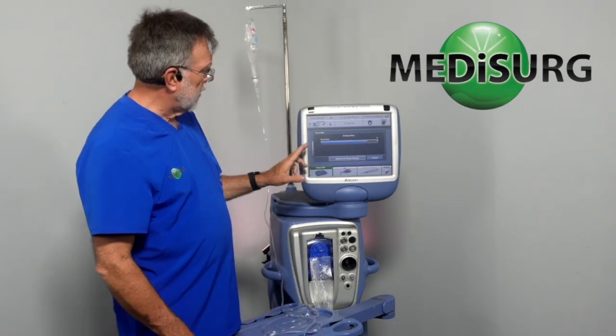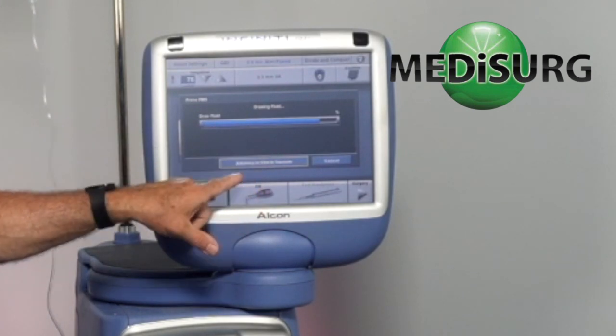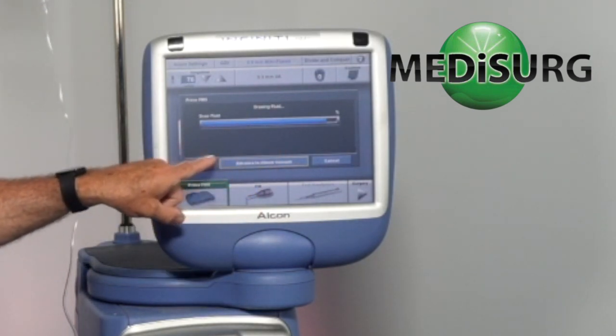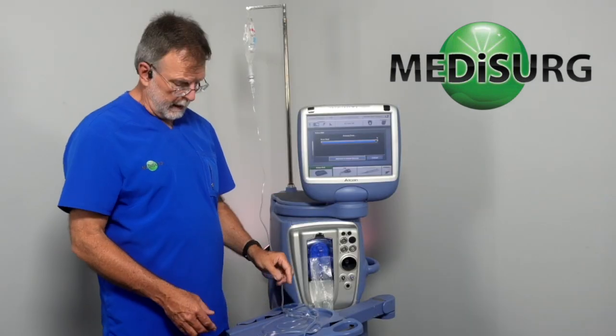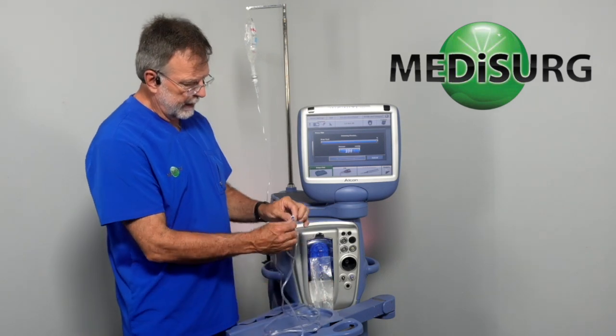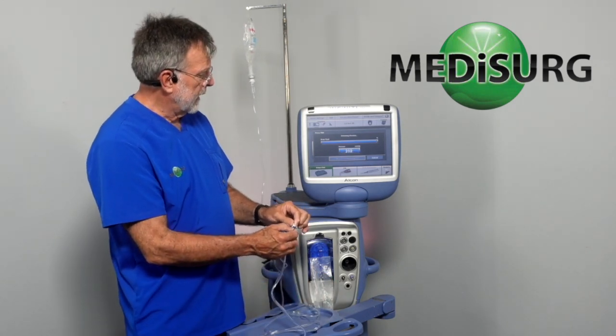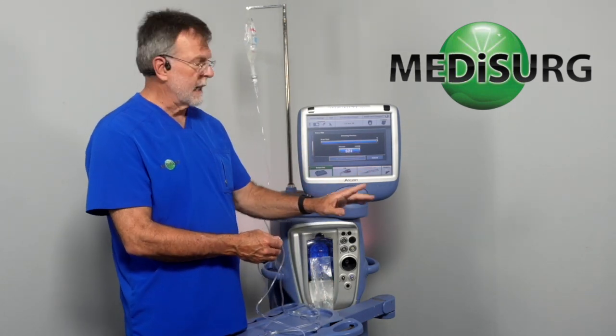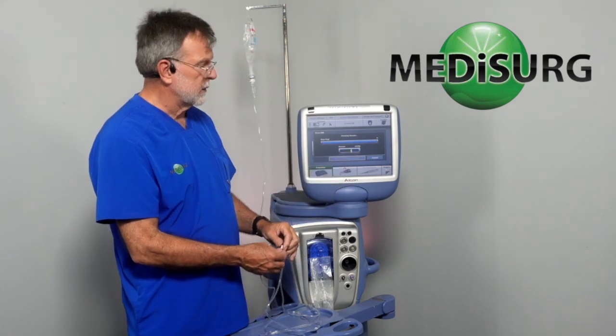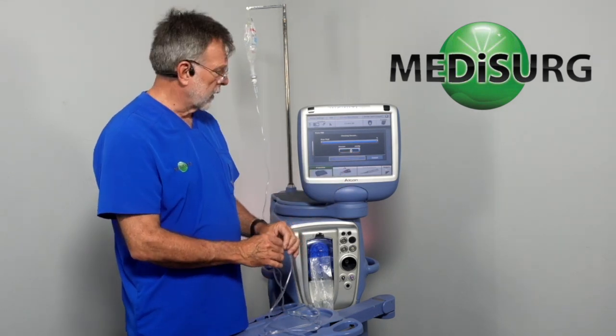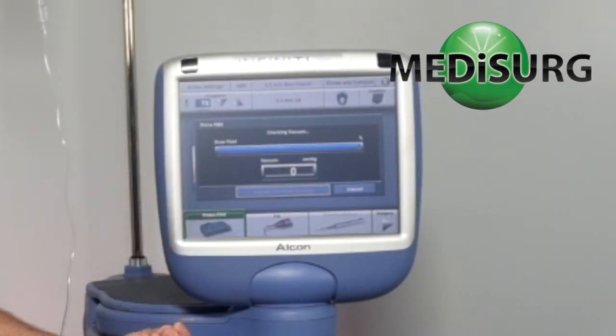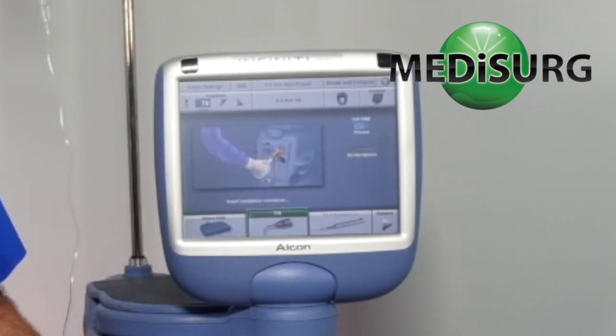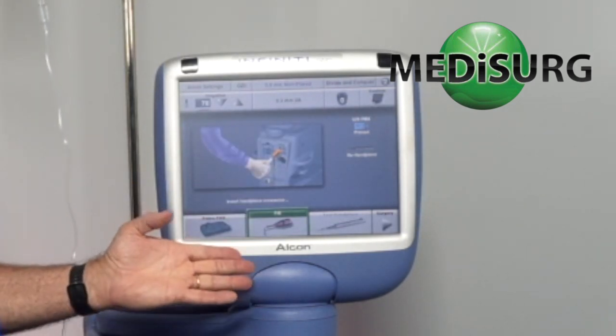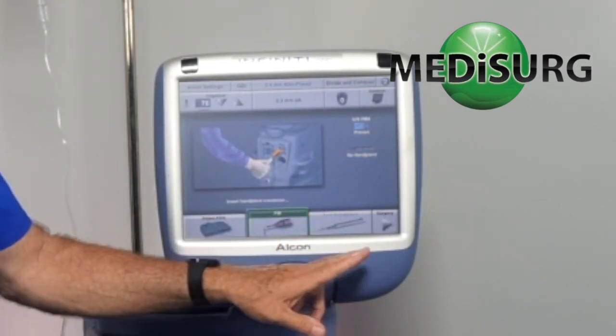Okay, the system is now finished drawing fluid in a few seconds here, and then it's going to do a vacuum check. It's going to make sure that our fittings are nice and tight, and then it's going to try to see how much vacuum it can actually pull. Here we're all the way up almost to 700. Everything's working very well. And then it vents, and when the pressure is vented and goes back to zero, we're now in the mode to go to surgery.